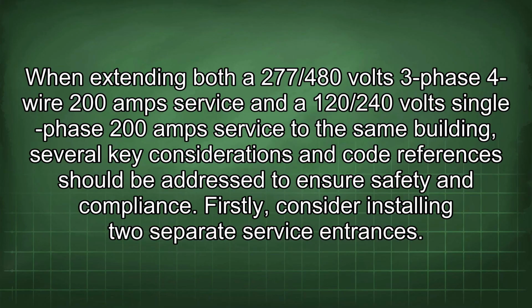When extending both a 277/480 volts 3-phase 4-wire 200 amp service and a 120/240 volts single-phase 200 amp service to the same building, several key considerations and code references should be addressed to ensure safety and compliance. Firstly, consider installing two separate service entrances.